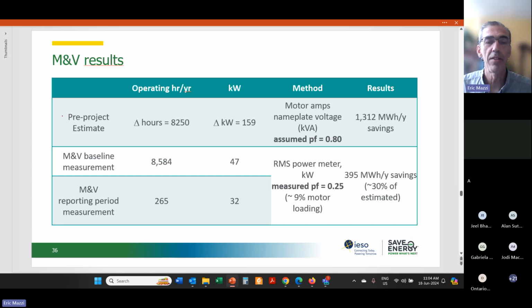So this table here summarizes the results. Okay, so let's talk about the pre-project estimate. The pre-project estimate of power savings and energy savings was you could go from 8,500 hours to 250 hours. So that's a change in hours of 8,250. It was 159 kW for those hours. And so the savings was 1,312 megawatt hours per year. So these came from spot readings of motor amps, motor current, and an assumed power factor of 0.8 on this induction motor. So that was the pre-project estimate, and the incentive was approved.